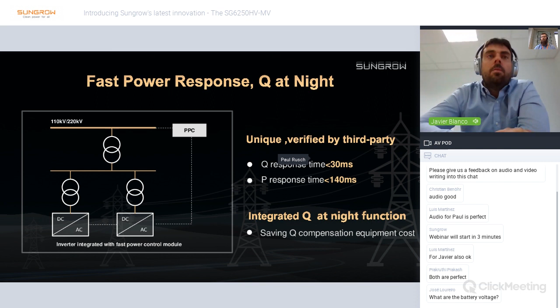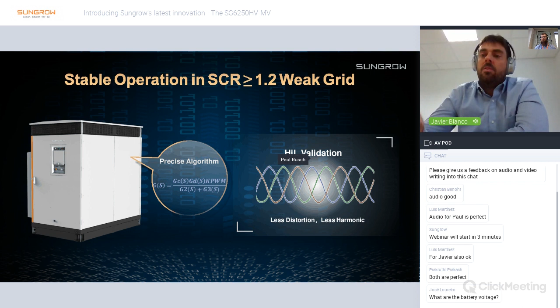Also something that has been considered specifically for this design is operation in countries with low SCR. For this there is a patent algorithm that has been validated through hardware in the loop. It enables the inverter to work in very low SCR ratios, meaning very weak grids. So it makes this central inverter able to operate in almost any grid in the world, even if the short circuit power is really low, the inverter can operate stably there.